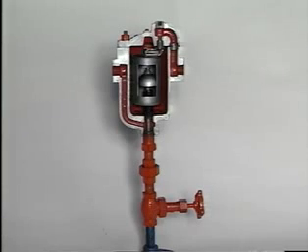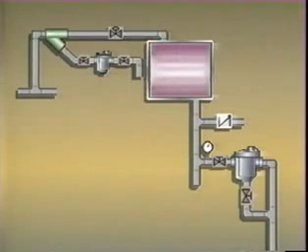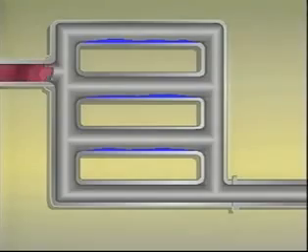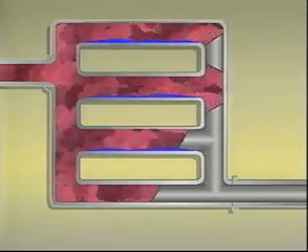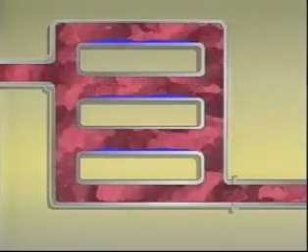Prevent the thermal shock that is generated by such a design by substituting a constant purge device, such as a differential condensate controller, for the steam trap. Condensate controllers maintain a positive differential pressure across the coil at all times. All the tubes will be fed from the supply end only, preventing the entrapment of steam and the resulting thermal shock.